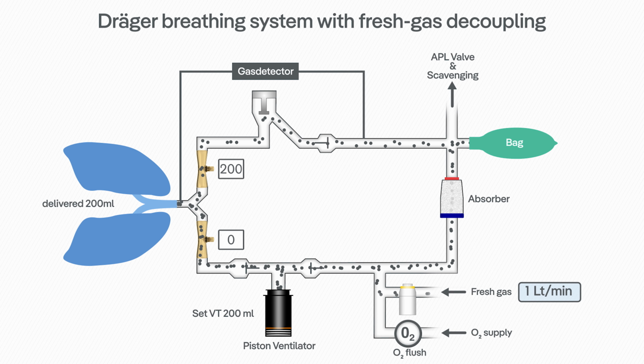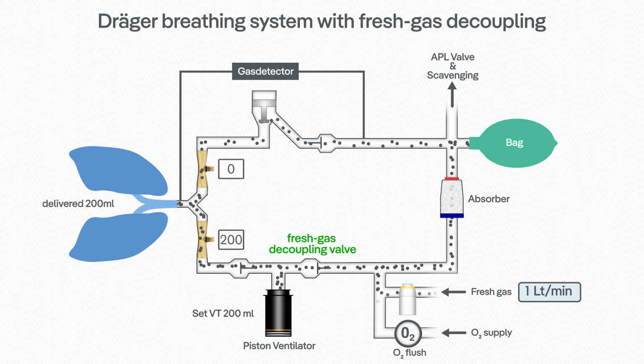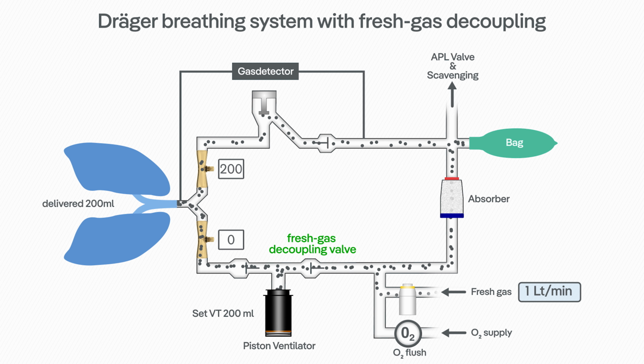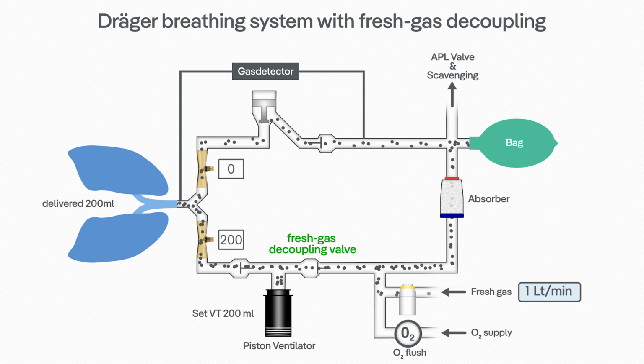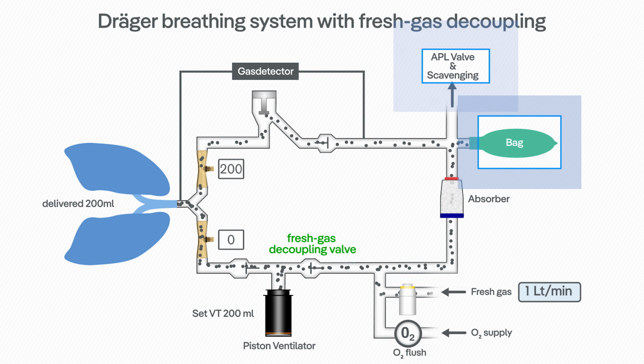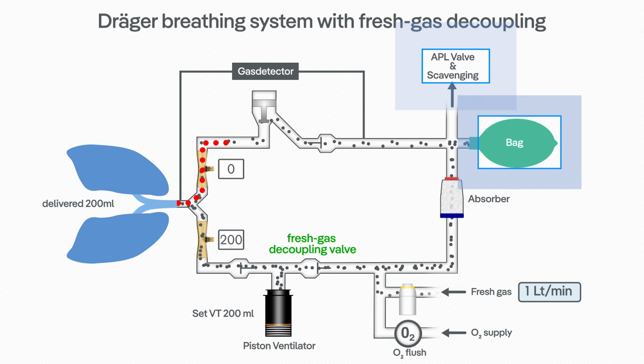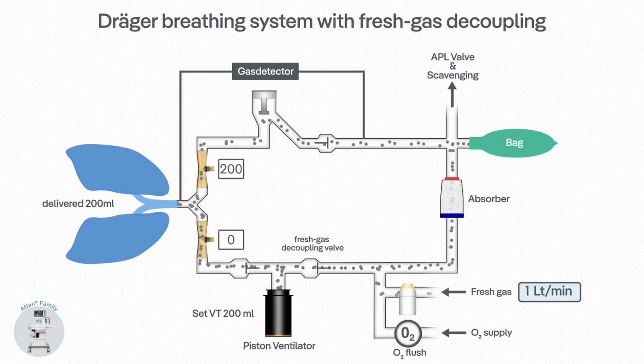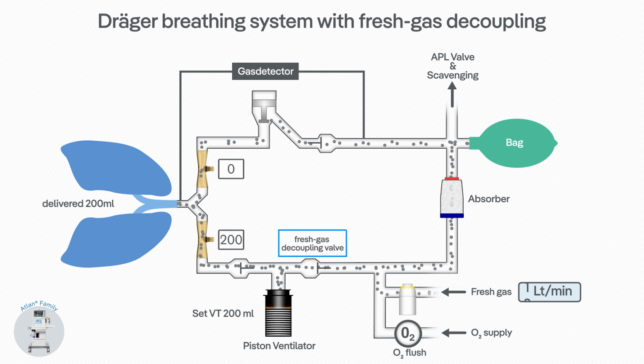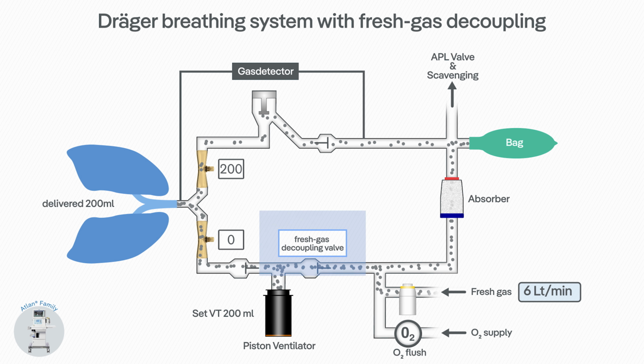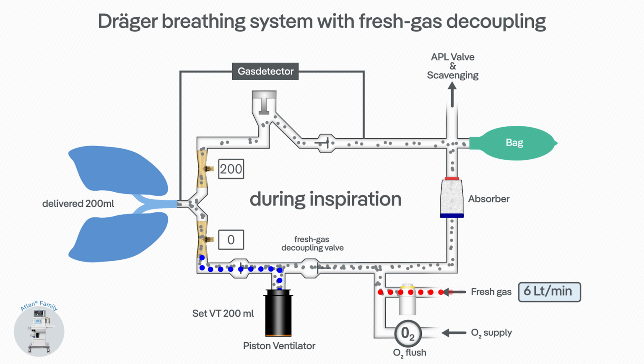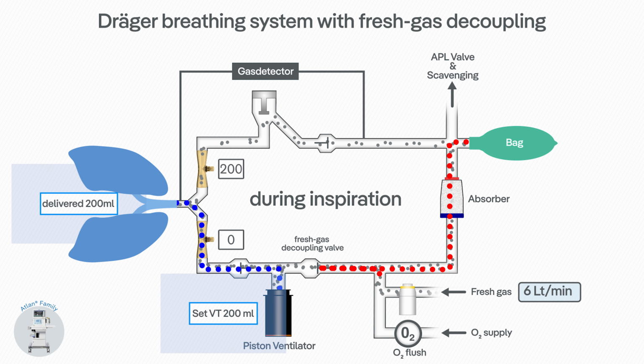The Dräger-specific solution, called fresh gas decoupling, is a much more direct and effective solution for this issue that ensures that the fresh gas can go to the reservoir bag and scavenging system, both during the in- and expiratory phases. In the Atlan family anesthesia devices, the fresh gas decoupling valve ensures that fresh gas flows during inspiration into the reservoir bag and the piston volume is delivered to the patient, so that even when the O2 flush is used, the generated tidal volume and airway pressure do not change.